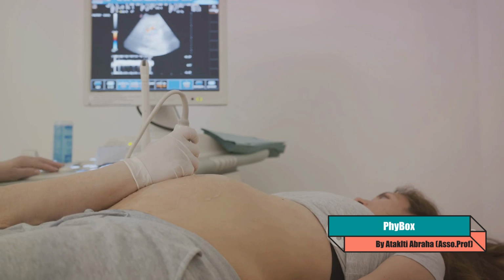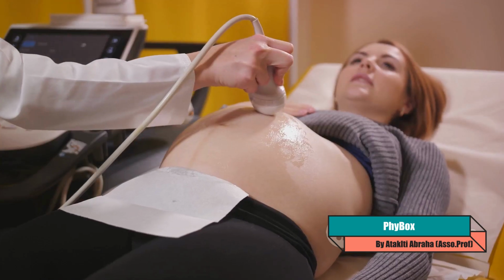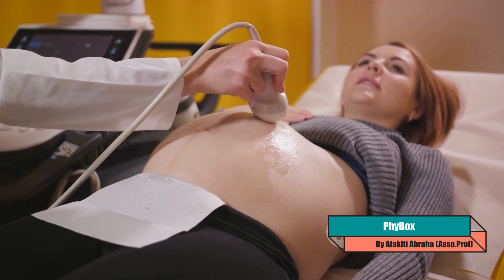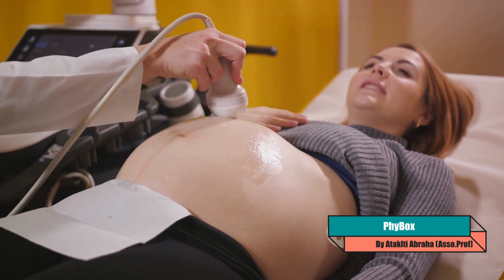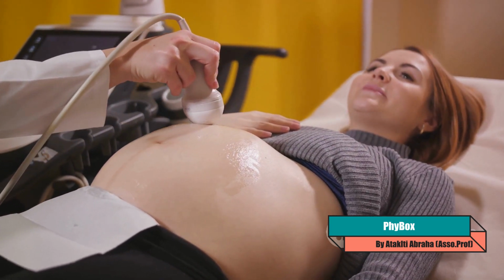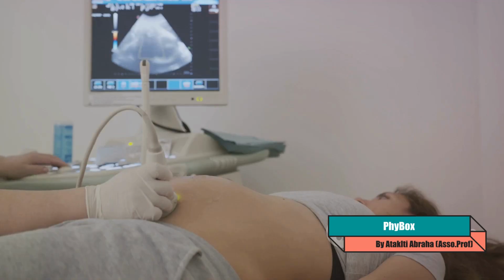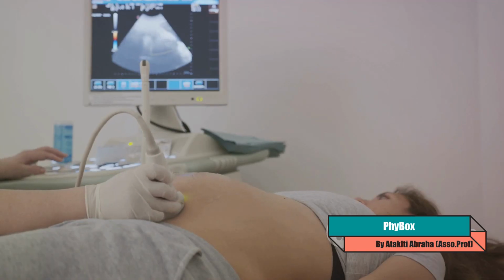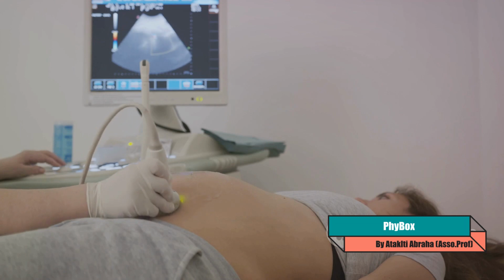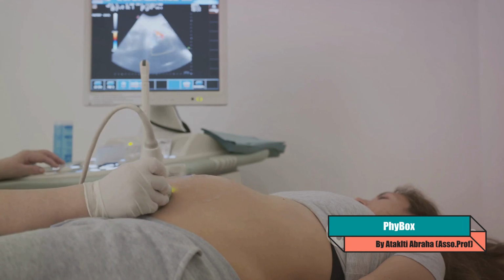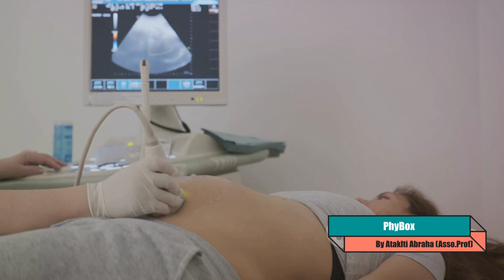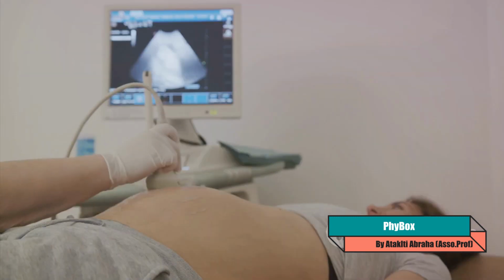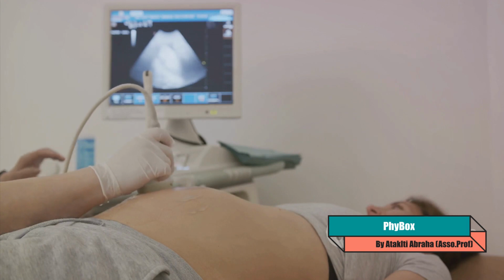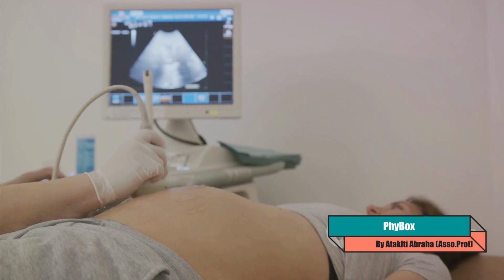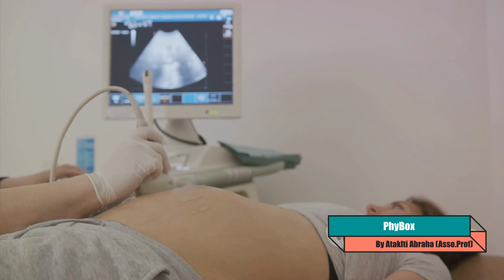Ultrasound, as the name suggests, uses sound waves that are beyond the range of human hearing, typically in the frequency range of 1 to 15 megahertz. But how does it work? Well, it's all about the echoes. When an ultrasound probe, also known as a transducer, is placed on the skin, it sends out a burst of sound waves into the body. As these waves travel, they encounter tissues of different densities. Each change in tissue type causes a bit of the sound wave to bounce back, or echo, towards the probe.